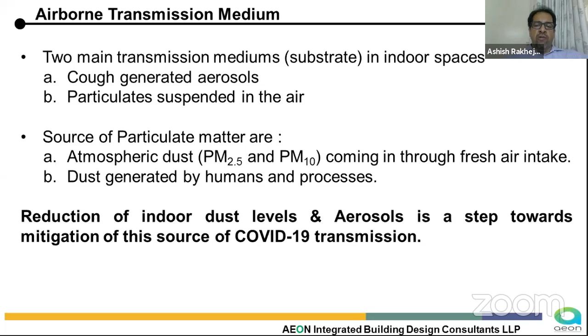If you look at ASHRAE, which is the Bible for all the air conditioning systems designed in most parts of the world, they recommend the following seven strategies: dilution, which is where the addition of outdoor air comes into the picture; the second is airflow patterns, the positive pressure, negative pressure areas, and how the air is flowing -- it's not only about positive or negative pressure, but also that there's no haphazard movement of air inside the occupied space, it needs to flow in a certain pattern; the third is the pressurization I spoke about; the fourth is temperature, then relative humidity, filtration, and finally other strategies like UVGI and so on.